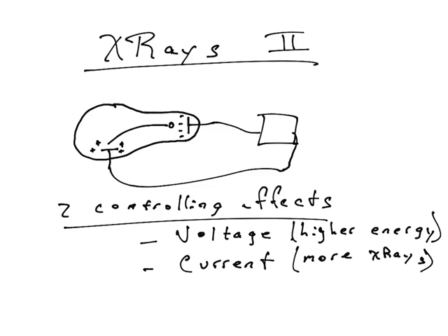So you had to wait for enough X-rays to hit the film to create the image. Well, now we know, of course, if we increase the current into this machine, that'll allow more electrons to be sent away. More electrons being sent means more X-rays will be produced. And if more X-rays are produced, that's more light hitting the film at once.